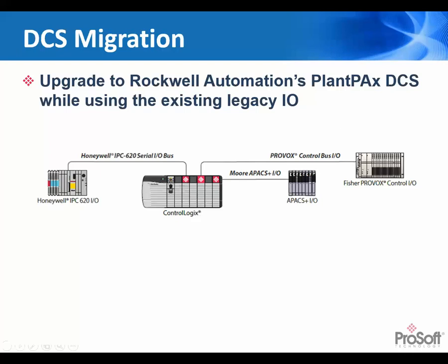So if something did go wrong or it wasn't quite working properly, you could then put the legacy controller back in place to control the I/O. Verify your code, and of course, if everything was okay, then you can begin to switch it back over to controlling, and then remove the legacy controller with the modern PlantPAX system.